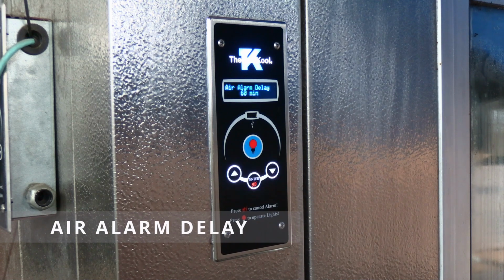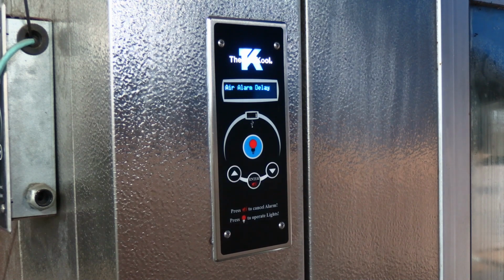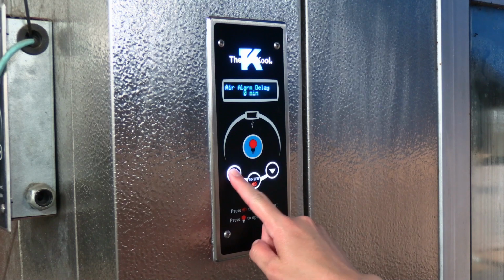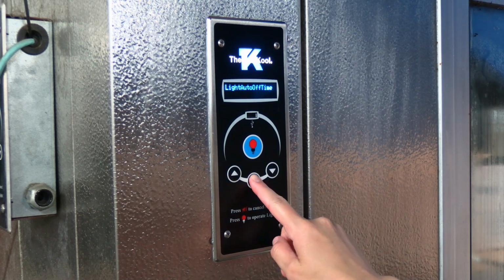Air alarm delay. This option allows you to select the time delay between when the temperature rises or drops below the alarm temperature set in the previous displays. This period of delay is to allow the cooler or freezer to regain correct temperature in the instance of elevated traffic in and out of the walk-in, causing temperatures to temporarily increase. The default range is from 0 to 60 minutes. To change the minutes, press the up or down arrow, then press Enter.